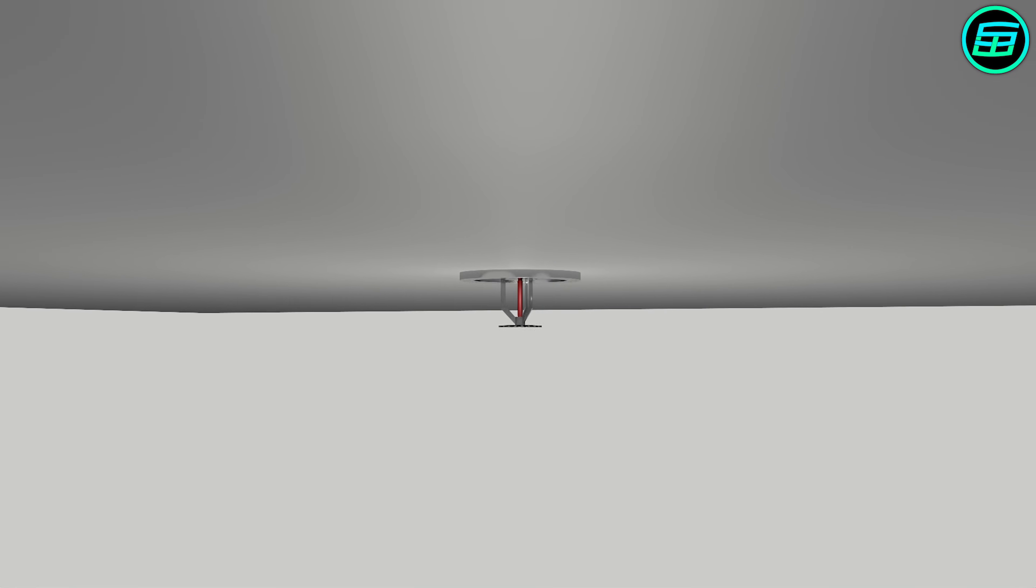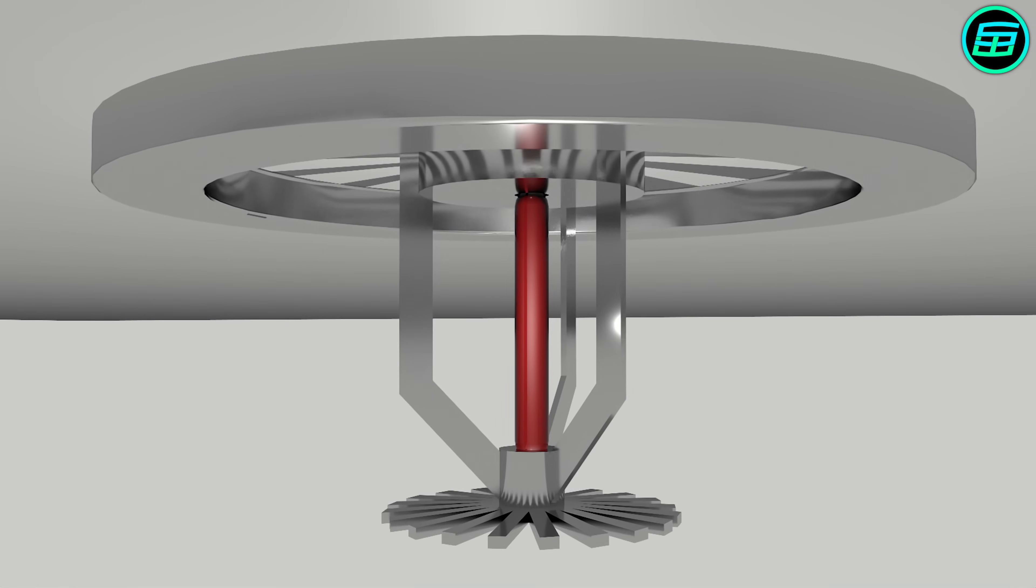There are different types of glass bulb filled with different liquids and these are color coded. Orange bulbs have an operational temperature of 57 Celsius or 135 Fahrenheit. Red bulbs 68 Celsius, 155 Fahrenheit. Yellow bulbs 79 Celsius, 175 Fahrenheit.